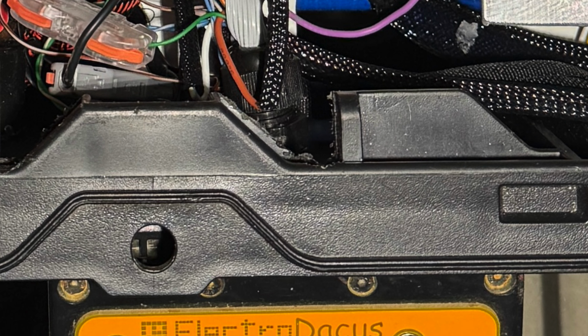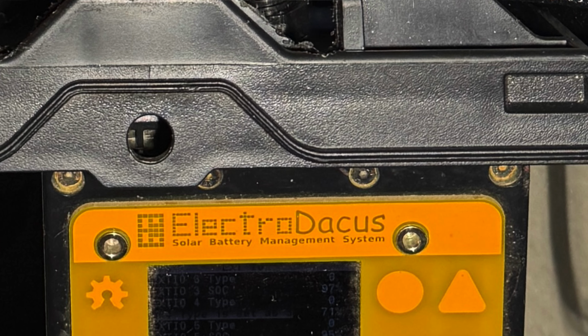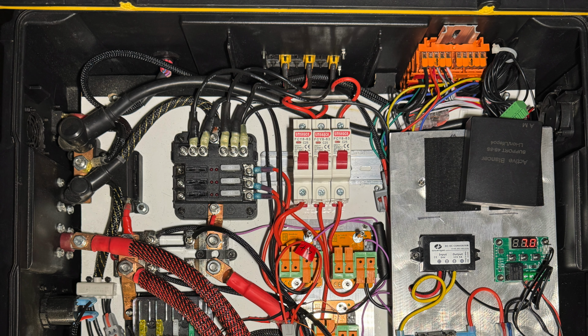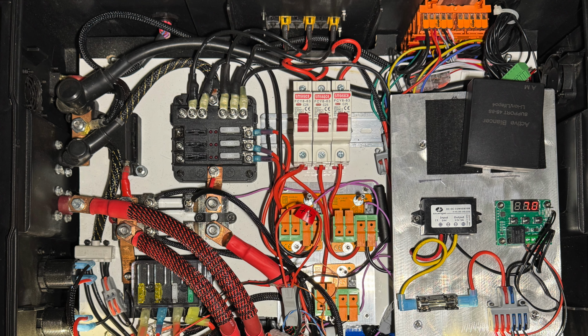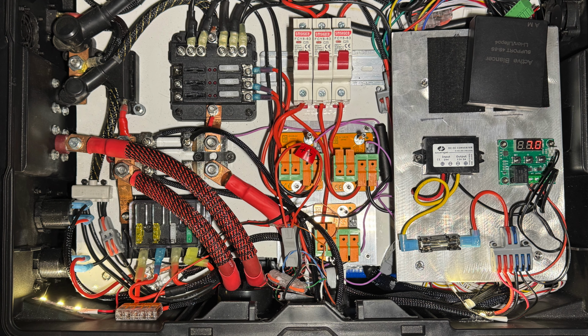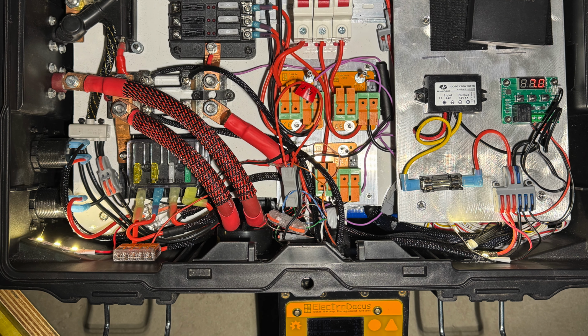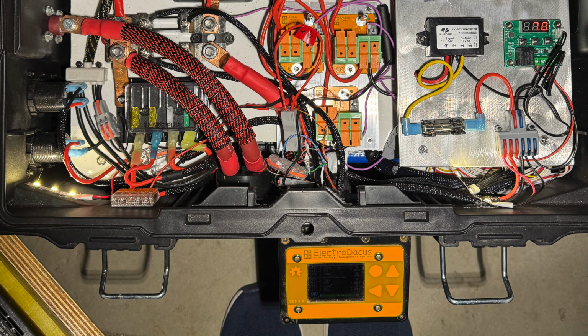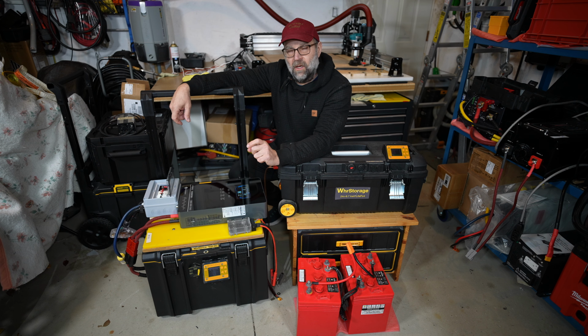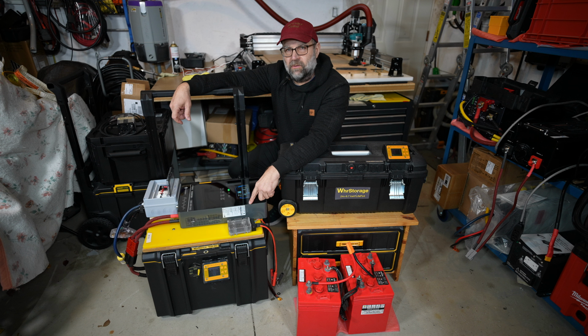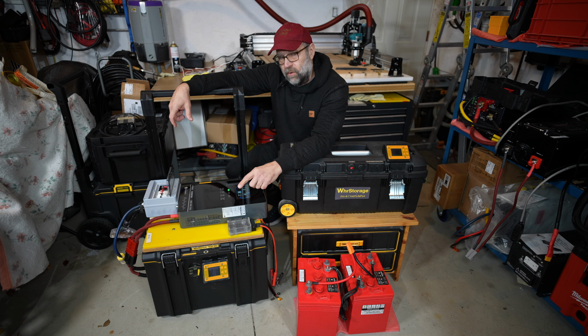But with this ElectroDacus, we can do better than that. We can now dictate, because it has 4 to 6 open or closed circuits that you can designate for different things. One we haven't touched yet would be for a generator. A traditional inverter charger has what they call dry contacts that start your generator when it gets down to a low voltage. Well, the ElectroDacus can do that as well.